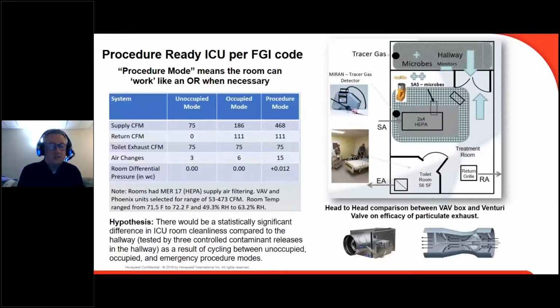And so basically it was head-to-head VAV box versus Venturi valve in this space, along with the proposal of let's go from unoccupied, occupied to procedure mode, right? And like I said in the past, in a number of these spaces, if you want to maintain good directional flow, a lot of times what the hospitals will have to do is increase their air change rates, right, in order to maintain direction. Well, that's not an option necessarily for most ICUs, right?